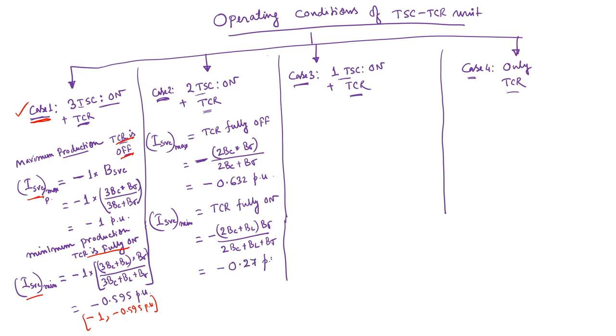So therefore one can conclude that we consider these two extreme ranges: one is TCR fully off, another is TCR fully on. So by partially conducting this TCR, it is possible to have a range of compensation, any value in between 0.632 to 0.27 per unit in this particular case.